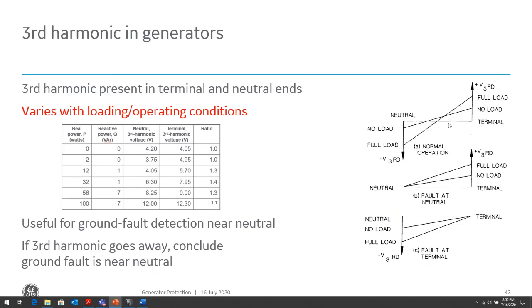In the drawing, in graph A, during normal operation, what we expect to see is a linear distribution of that third harmonic voltage from the neutral of the generator to the terminal of the generator, with maybe about 50% of the winding. If we look at the voltage at 50% of the winding, obviously we can't read that voltage, but if we did, it would be about 0 because of the linear distribution of the third harmonic voltage from the neutral to the terminal of the winding. So what happens is, if you have a fault at the neutral, the third harmonic voltage drops to 0, because now that neutral is basically grounded. So you move the neutral point of that third harmonic voltage.